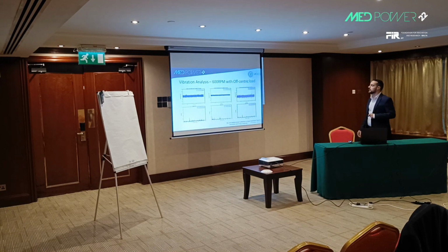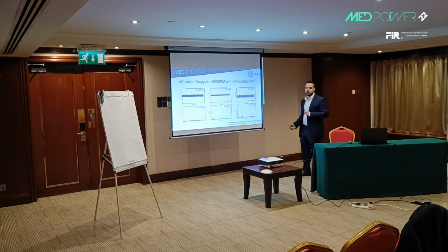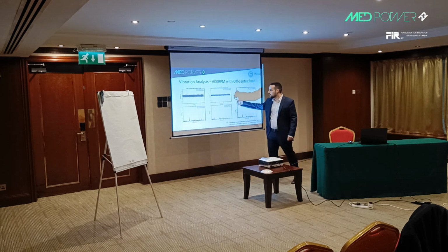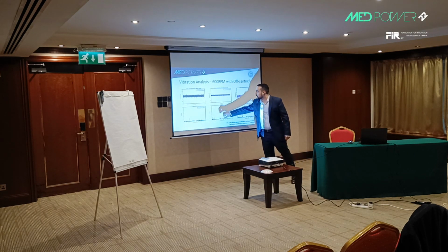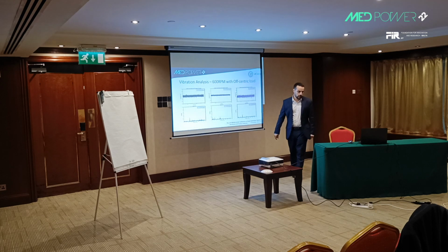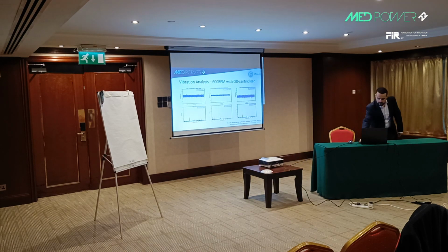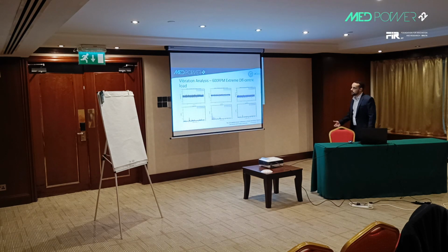In the vibration analysis, you can see that it's more pronounced and can be detected quite easily, with this increase in harmonics and also in the time domain. With an extreme off-centric load, it can be detected much more easily, and here we can see the differences between a small off-centric load and an extreme off-centric load.